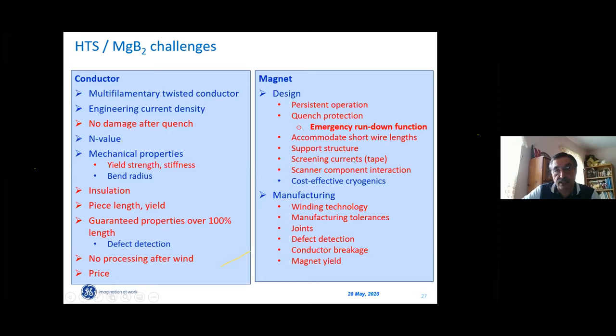ramp the magnet fast. And we need to address typical issues of what we have in screening currents, component interaction, because we cannot use tape. We need multi-filamentary conductor with twisted filaments. Otherwise, we induce eddy currents that will interfere with high-frequency gradient coils. And many other issues that we still need to address.